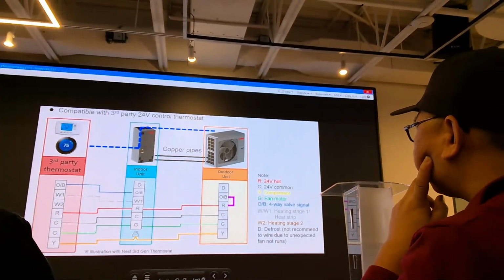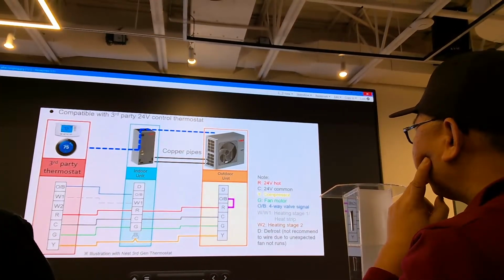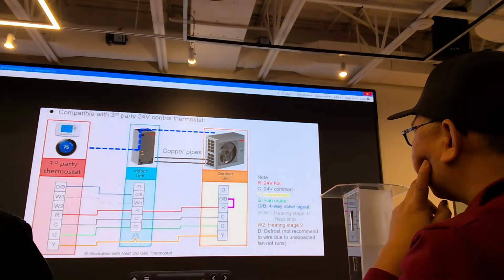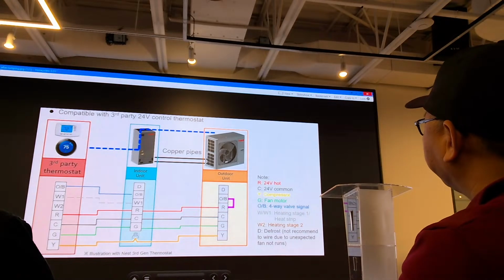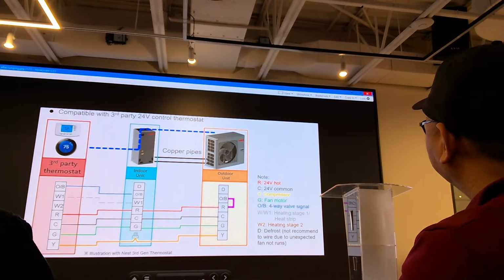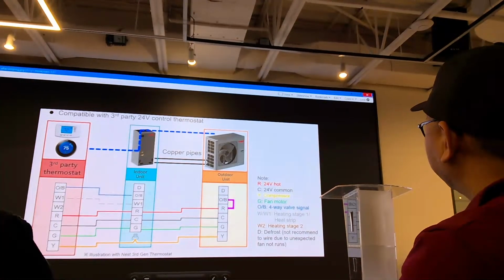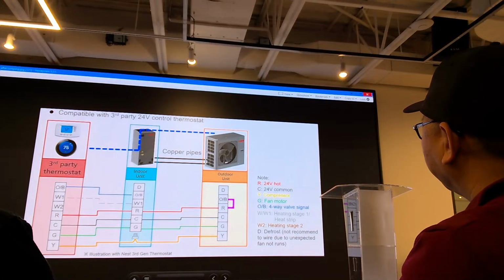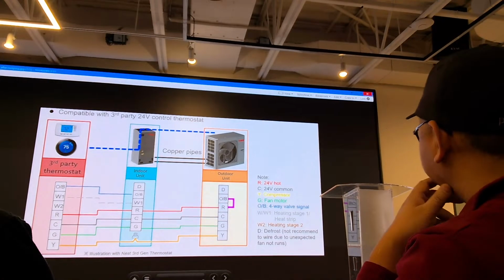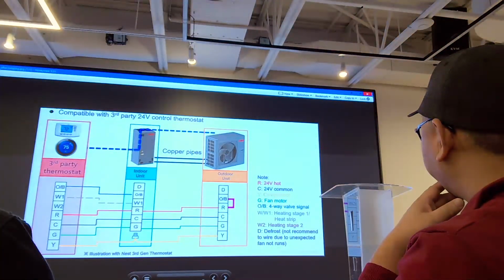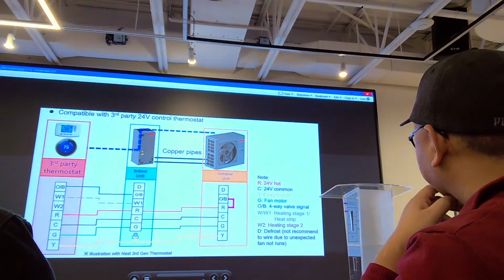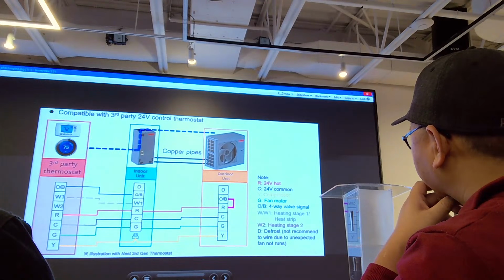Can I ask you a question? Yeah. When it goes from heating to cooling on the defrost, does it go while it's running, or does it shut off the unit? Could you say that again? When it goes into defrost mode, does it shut the unit completely and then start up defrost, and then it's finished and it comes out? Yeah. And the point is we need to make the reversing valve change direction, right? Right. In our control program, we make the compressor stop and then change over.